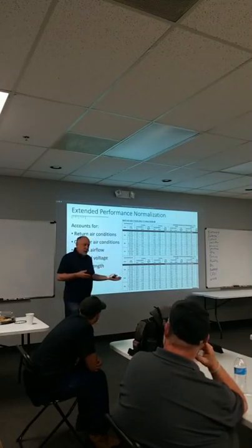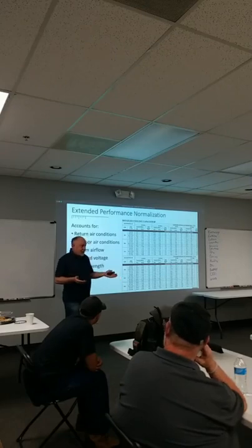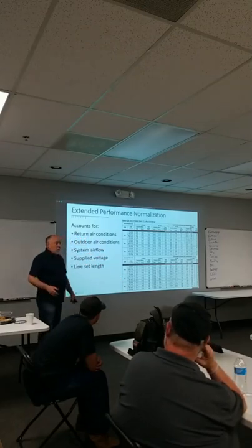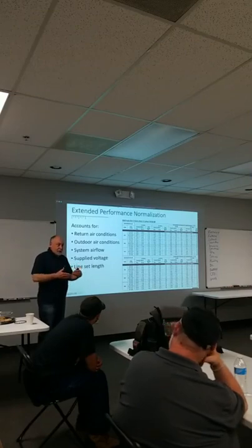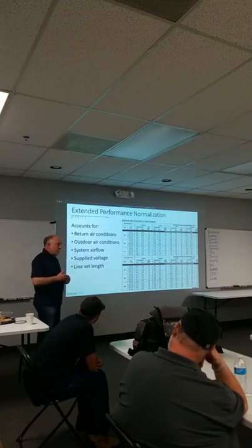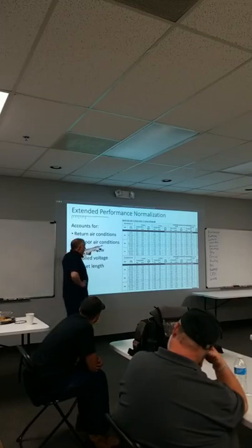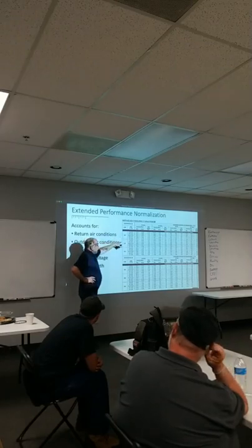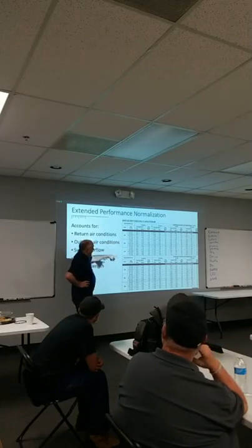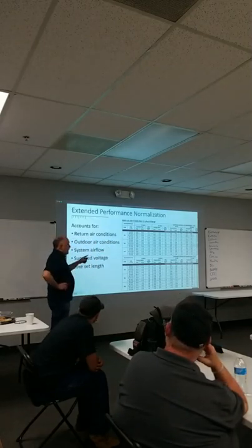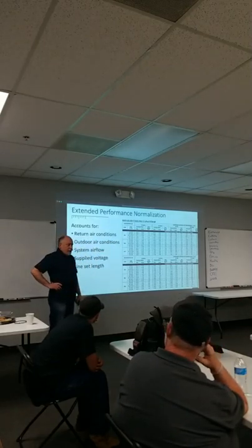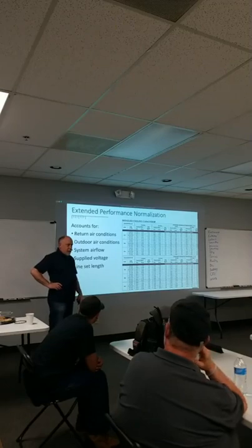So Measurequick does what's called equipment normalization. We actually calculate what your equipment capacity should be based upon what the current load conditions are. So we look at outdoor temperature, we look at return air, wet bulb and dry bulb, look at your target airflow, whether you're doing 350 CFM a ton, 400 or 450 CFM per ton. And we run all these calculations in the background to assure that when you're comparing your actual capacity to what's called the normalized capacity.